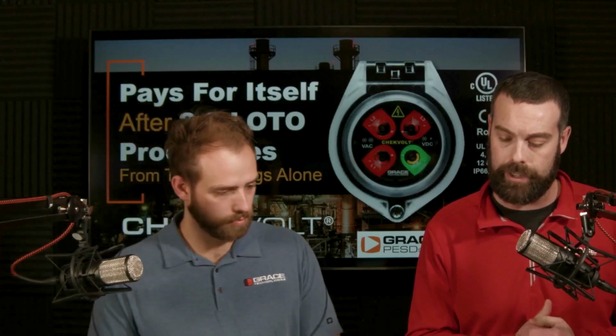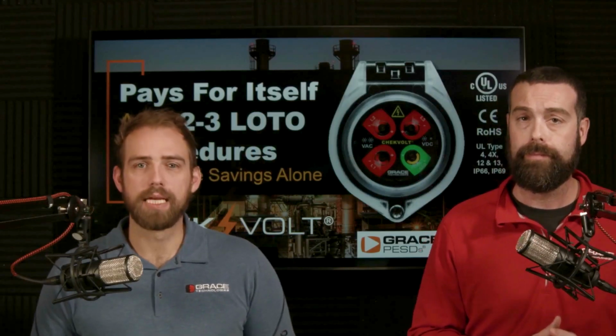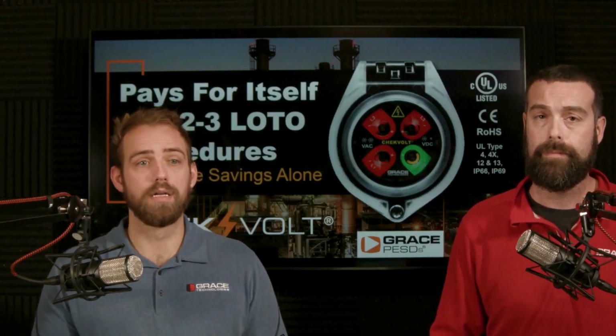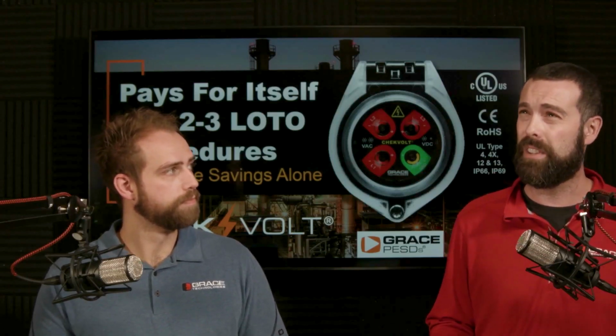So the first question is, how is this different to the VeriSafe from Panduit? It's a great question. So basically the main difference between the VeriSafe from Panduit and our ChekVolt, or permanent electrical safety devices, is the Panduit VeriSafe is a push button. So you push a button and then it does the electrical lockout tagout continuity testing, and it's all internal to the device itself. UL listed, UL 1436 listed. I believe SIL 3, I believe.